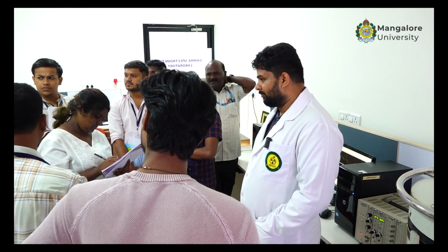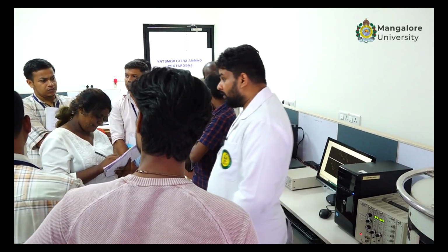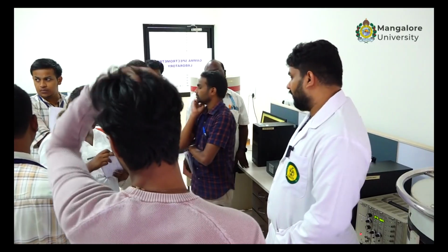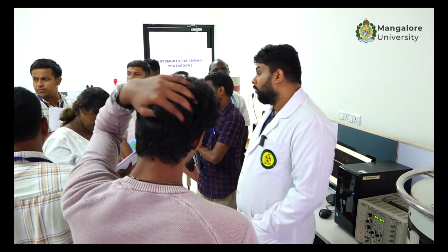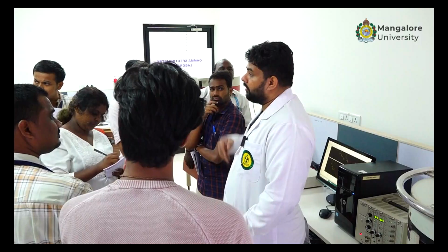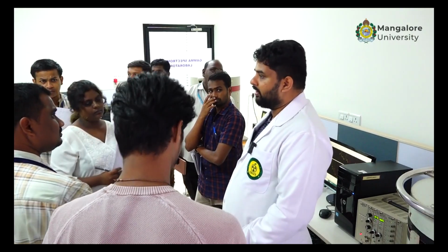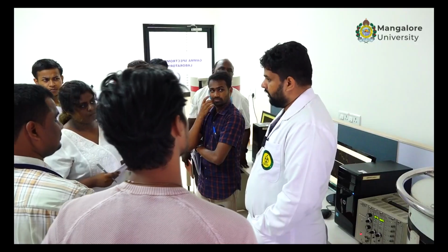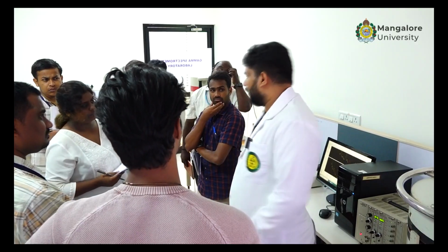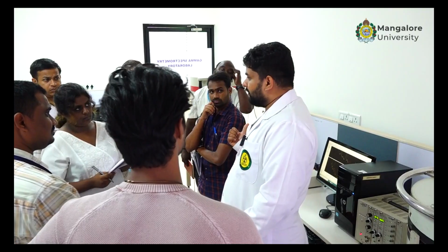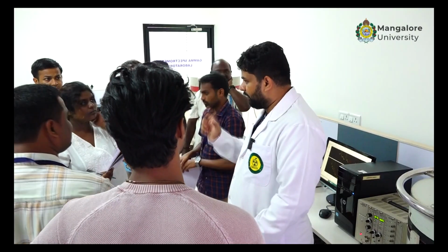I have one question. How often do you measure the background? Sir, every 15 days. How long is the background? For HPGe, we measure it for 60,000 seconds, or sometimes even 82,000 seconds. That is basically 1 day. For this one, 10,000 seconds, because I count the sample for 10,000 seconds. So background and sample I keep for the same time.